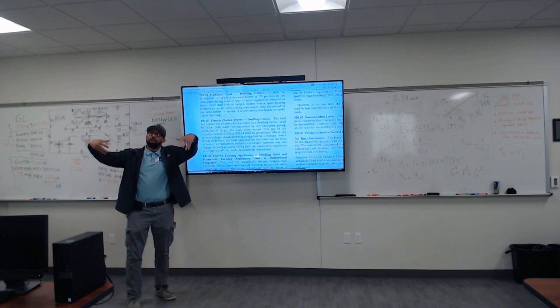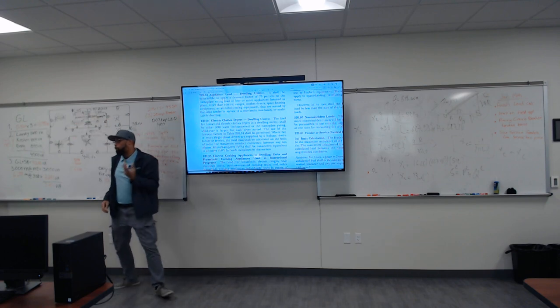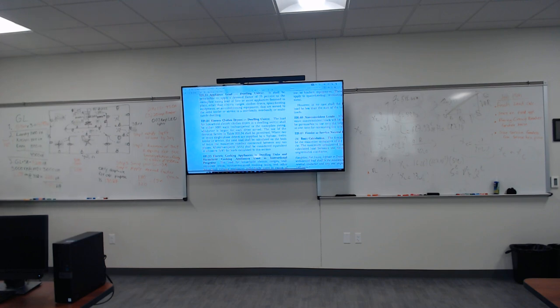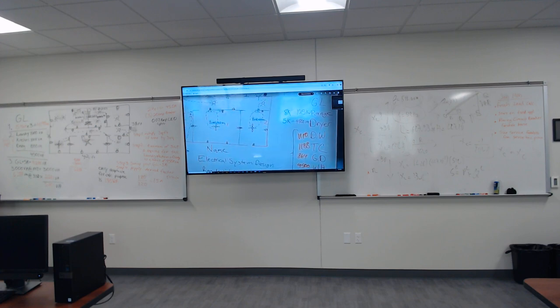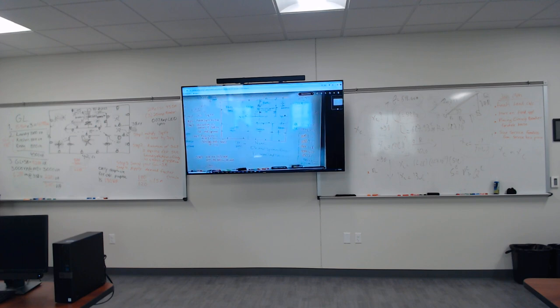So let's figure out what our dryer size is, or our watts, okay? We're taking information from old references, all right? Let's see here. A lot of these systems, so we'll be making up these numbers. All right, our dryer nameplate was 4,800 VA. But since it's 4,800 VA, what are we gonna use? 5,000. So, fellas, number five, you're going to write down 5,000 VA, not the nameplate under 5,000. If it was more, then we'd use that value. But put 5,000 in there.